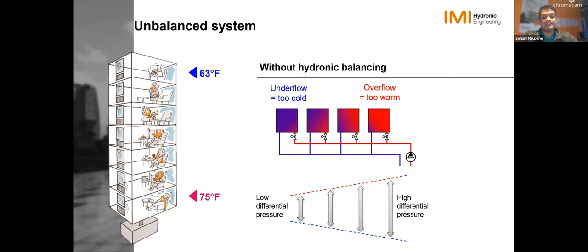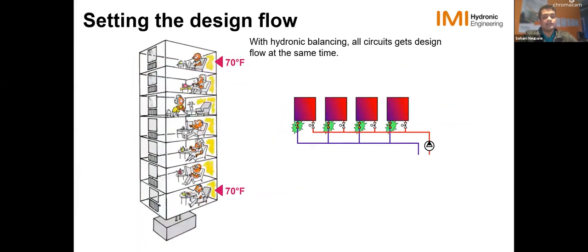Okay, and with balancing, what we are doing is we are basically restricting the flow in the circuits. So now, since control valves were overflowing and underflowing, we go in, we add balancing valves in here. So what we're doing is we're adding resistance on each of these circuits, wherever we're adding the balancing valve, to make sure that we do not overflow. So we just have the right amount of resistance you need to make sure you get the flow that you are looking for your design condition.